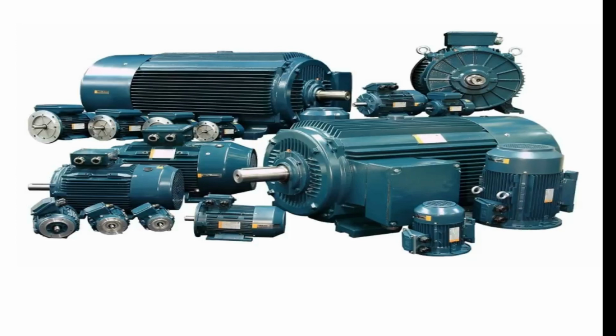When synchronous motors are considered, wound field and permanent magnet synchronous motors have higher full load efficiency and power factor than induction motors, but the size and cost of synchronous motors are higher than induction motors for the same rating.